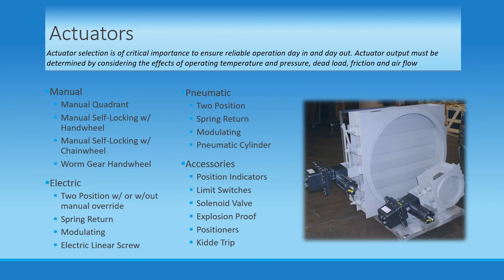Actuators can come with a variety of accessories to complement and expand their capabilities. Position indicators relay blade position — open, closed, and in between — to a central computer control or station for real-time monitoring. Limit switches can supply similar blade indication and can be offered with hazardous environment ratings. Solenoid valves and positioners can control a modulating actuator using an input signal for precise operation, and in conjunction with position indicators can provide complete real-time and/or moderated control using automation. Weather and explosion-proof housings are available for vulnerable operations. We have experience mounting Kidde trips to heavy-duty industrial control dampers allowing for immediate closure in response to pressure inputs. We have mounted and tested hundreds of different types of actuators for a variety of exacting environments with full engineering support.